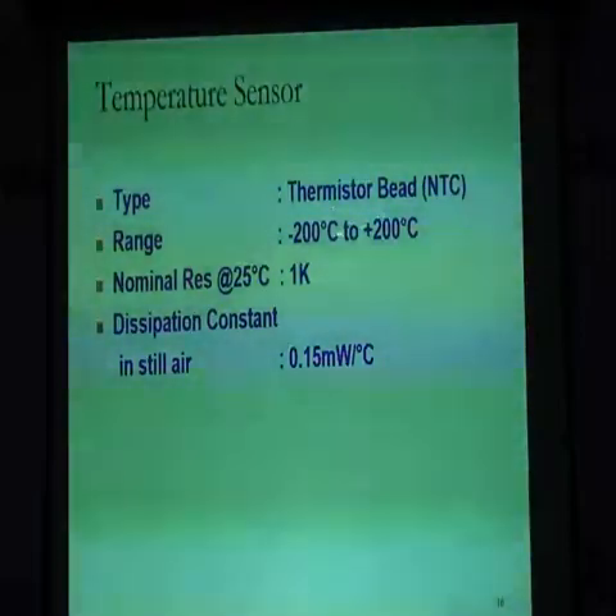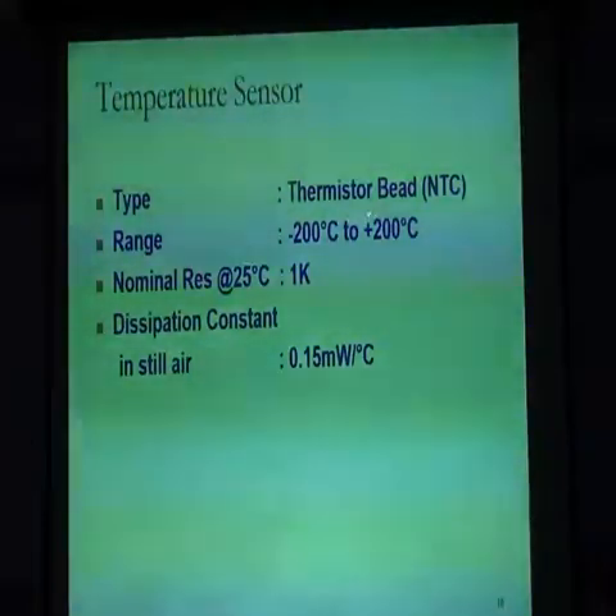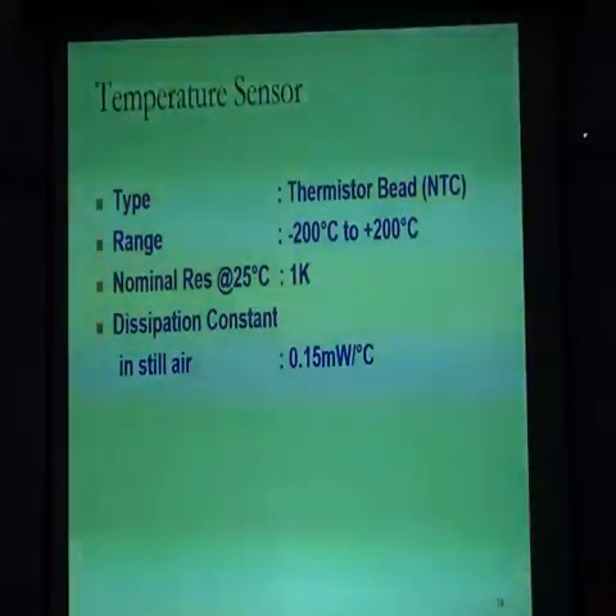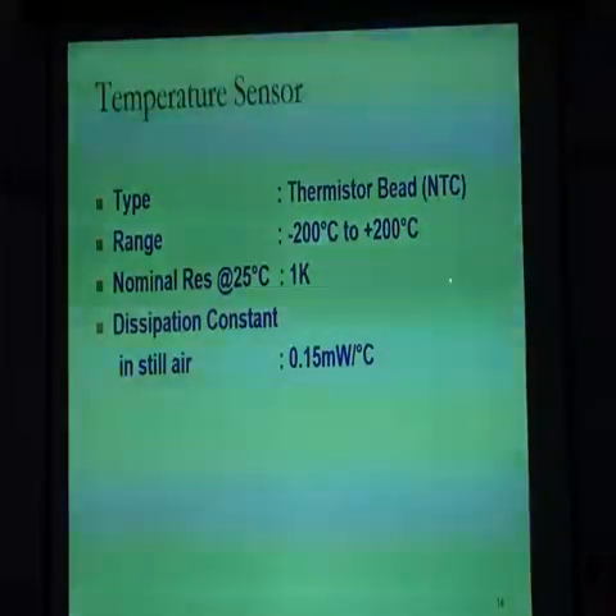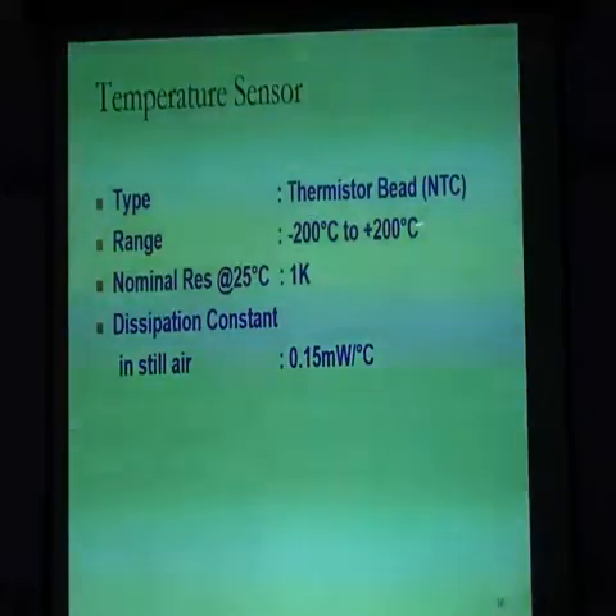So the thing is, when something goes into the atmosphere, you must know there are radiation factors which affect it. So the smaller the mass, the smaller the self-heating due to radiation effect. Earlier we were using an RTD, which was bigger in size. Bigger size means more thermal mass, so more radiation effects, more self-heating, so less accurate temperature results. This is very small, that's why we are achieving very accurate temperature results.